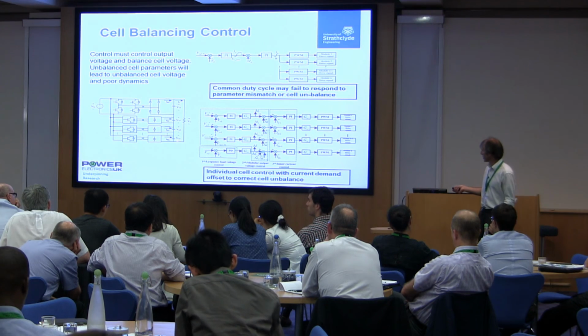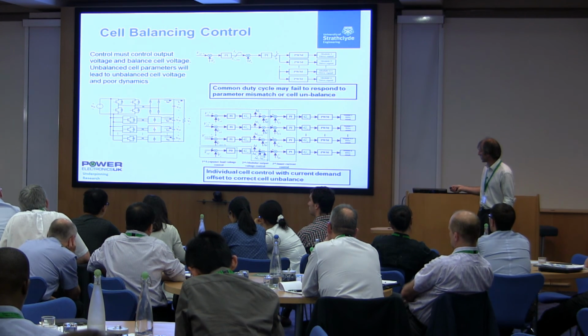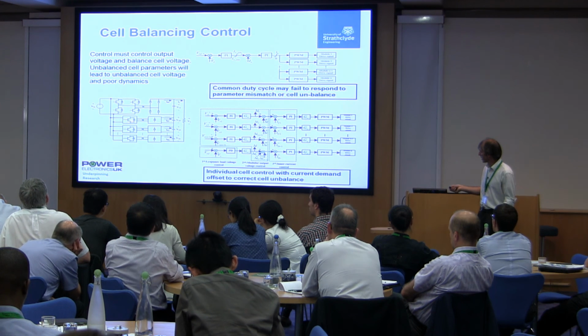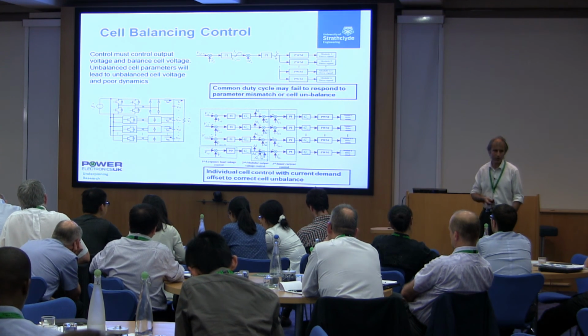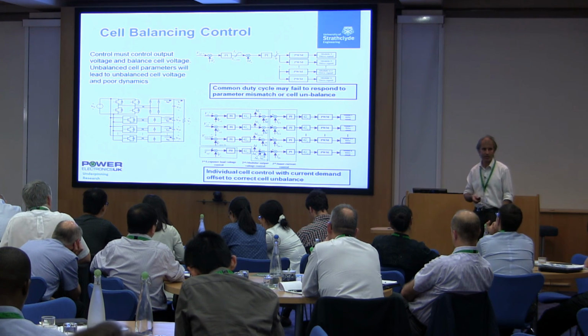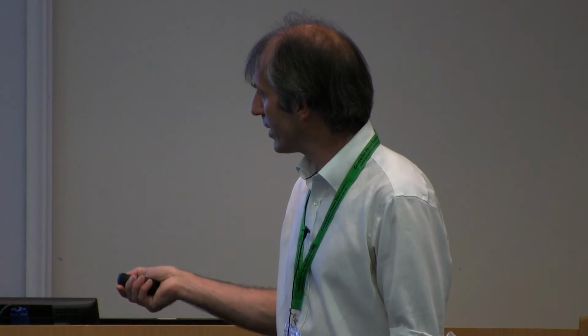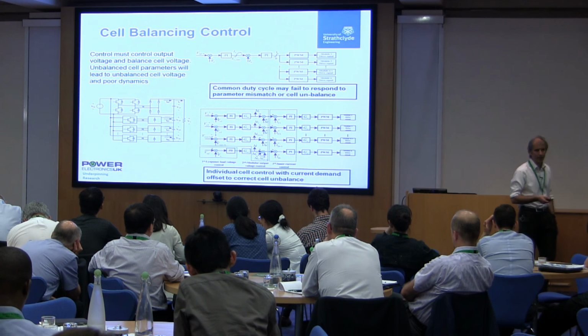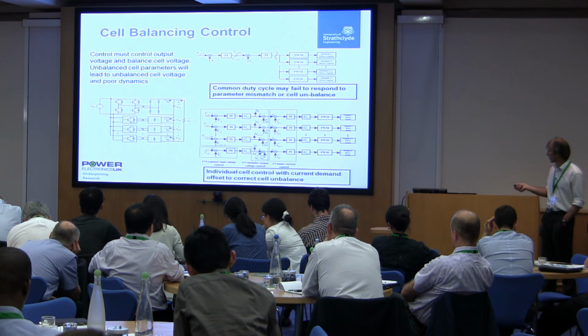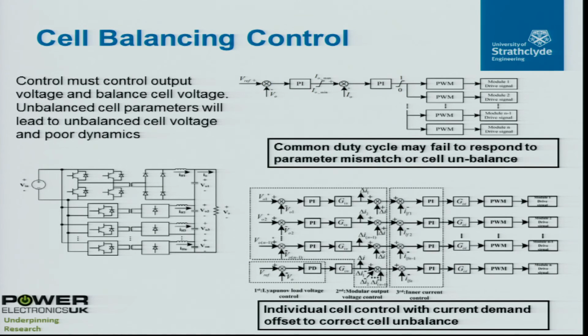So control schemes which regulate the output voltage and then regulate the individual cell voltage with, again, current control loops to make sure that that voltage is itself regulated start to become necessary. And that results in a fairly large-scale requirement for transducers and feedback and relatively complicated control, as you've got an output voltage control to control the total output, and then the approach adopted here was to have a master controller and then to add offsets to the current control loops of each individual device in order to drive them back to the same DC voltage.